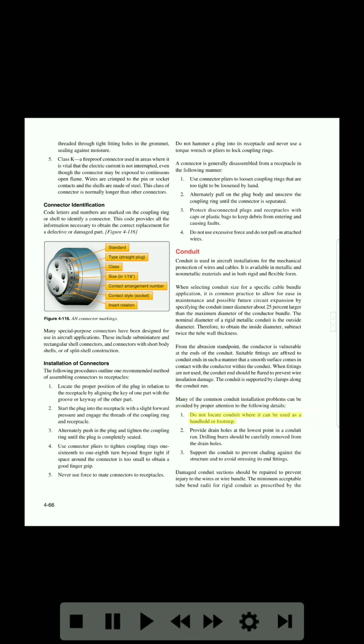1. Do not locate conduit where it can be used as a handhold or footstep. 2. Provide drain holes at the lowest point in a conduit run. Drilling burrs should be carefully removed from the drain holes. 3. Support the conduit to prevent chafing against the structure, and to avoid stressing its end fittings. Damaged conduit sections should be repaired to prevent injury to the wires or wire bundle.